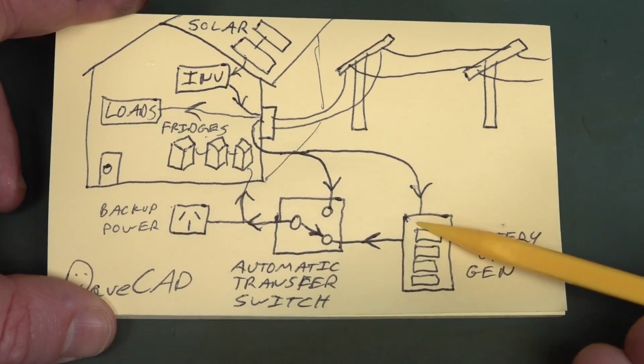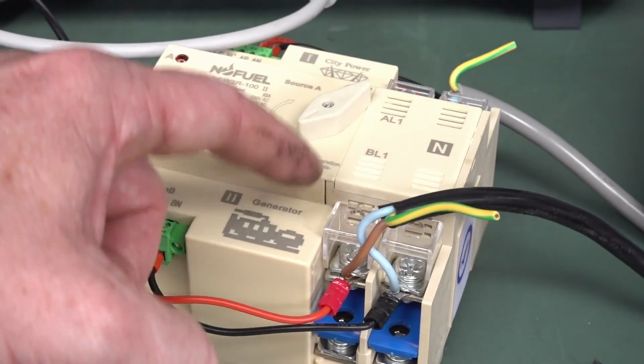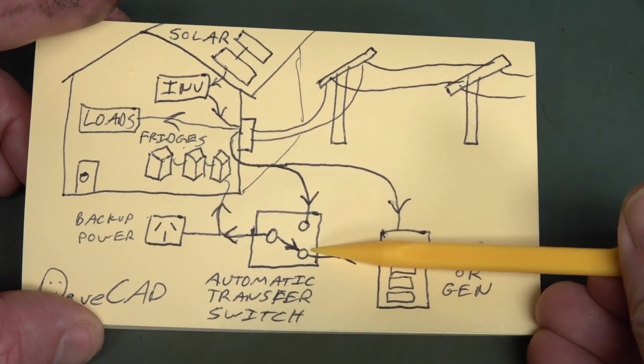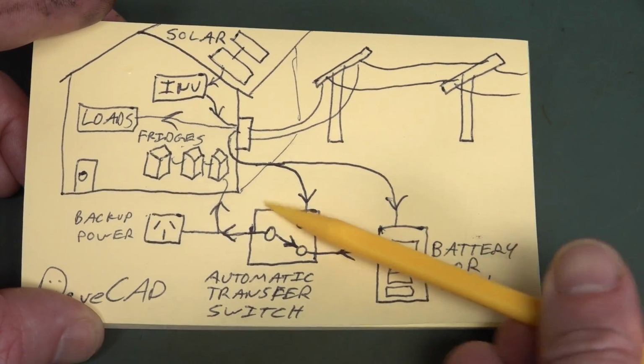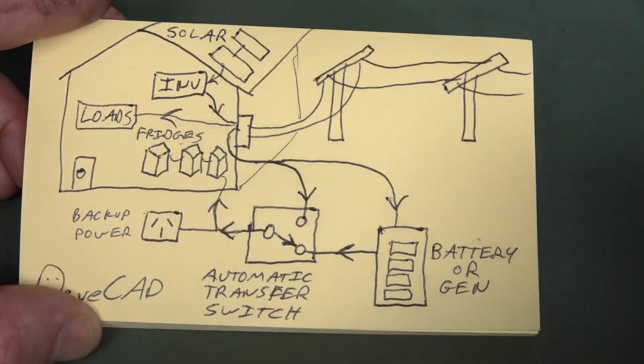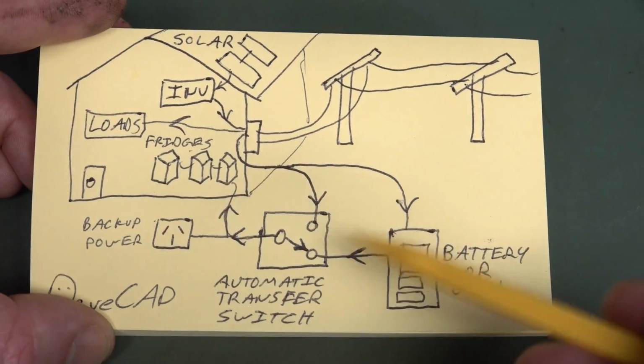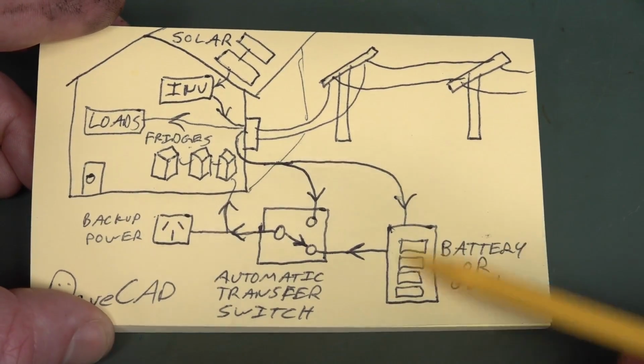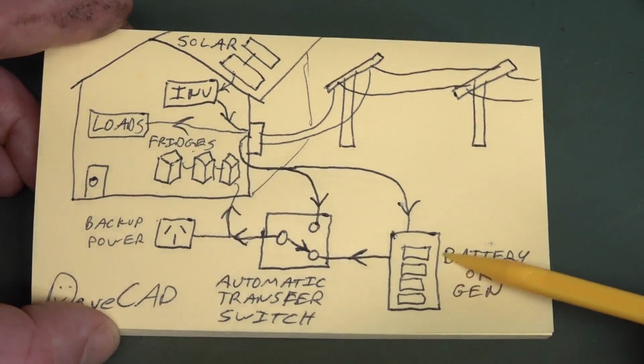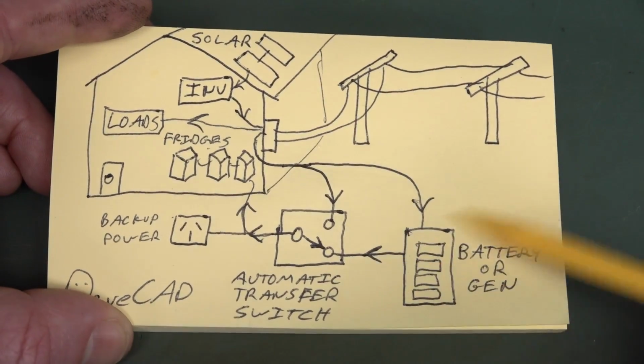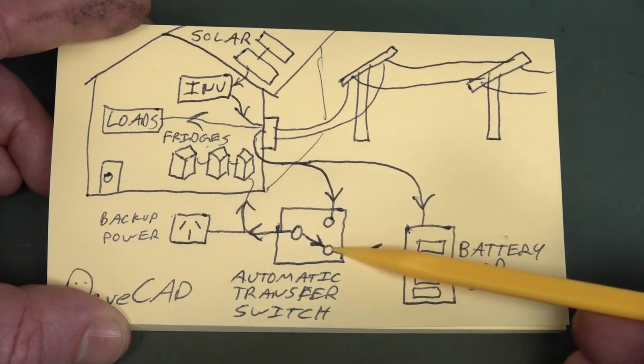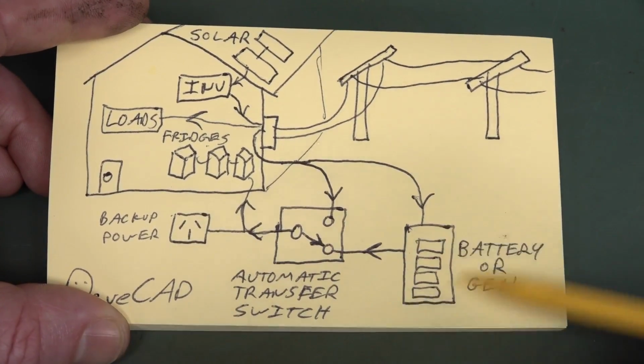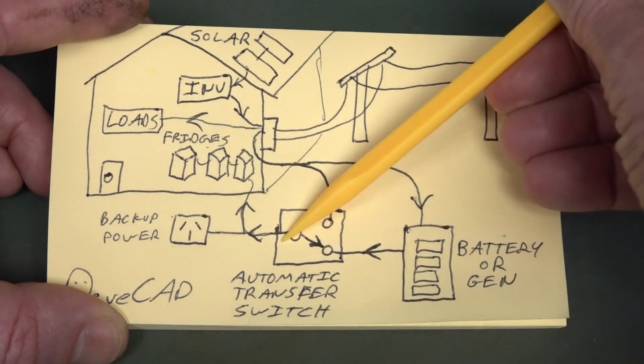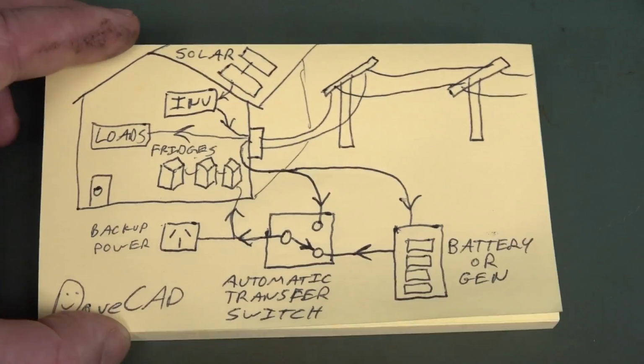If for some reason this fails, this automatic transfer switch will automatically detect that the generator input, which is the battery, has failed, and within about 50 milliseconds it'll switch over to the grid, keeping these fridges and freezers running regardless. Then as soon as the battery comes back online, say you fix a tripped cord and plug it back in, it'll automatically detect that the priority input, the battery system, is back up and switch from the grid back to the battery. That's what these automatic transfer switches do.